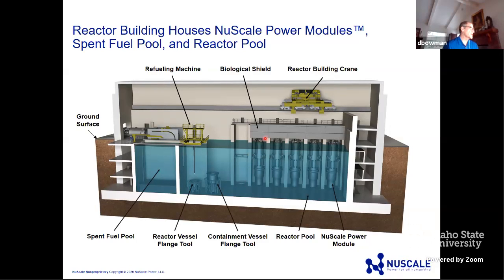Rather than refueling in place, we actually use the reactor building crane to pick up the module, and we disassemble it using this containment vessel flange tool and the reactor flange tool. When you come out of the reactor vessel flange tool, you take just the upper portion of the module and you move it to the dry dock, which is in the back behind the refueling machine here. I do have another overhead view that'll show that better. What's left behind is the lower part of the reactor vessel, and it contains the core.